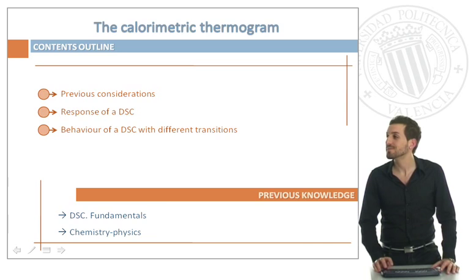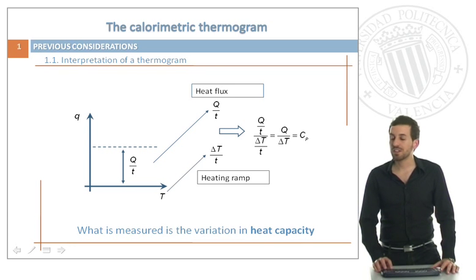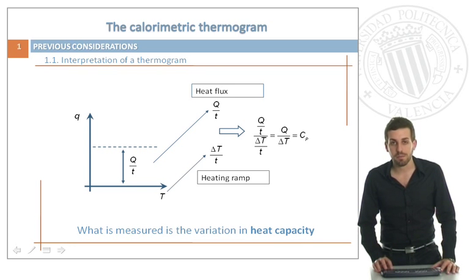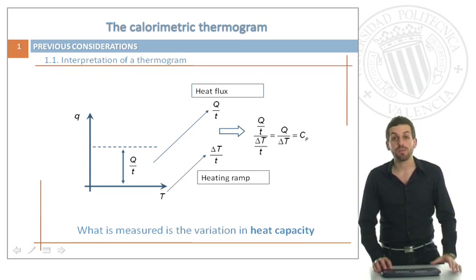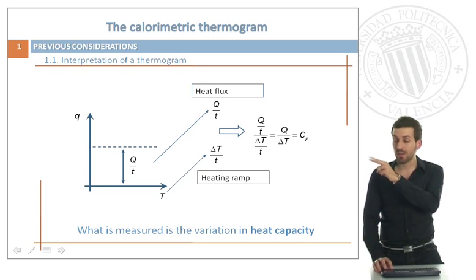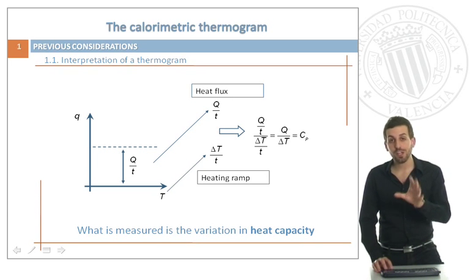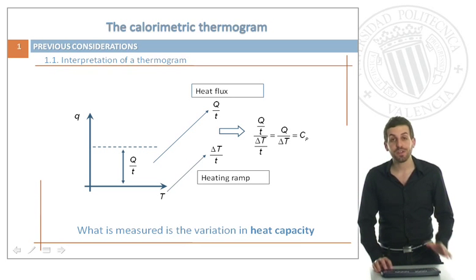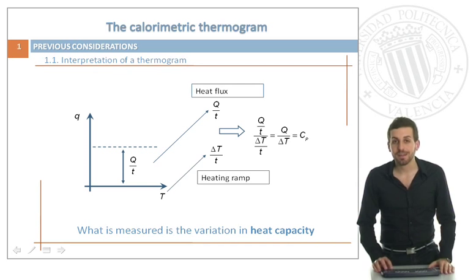The first question is: what is our DSC really measuring? The response that we obtain is the relationship between the heat flux and the temperature. If we divide both parameters, what we are really obtaining is the heat capacity. So, we are measuring variations in heat capacity.